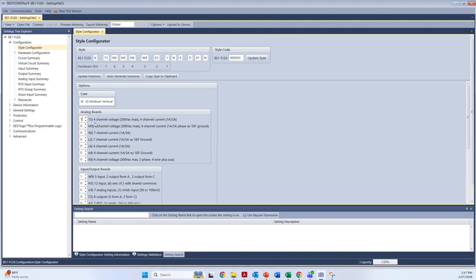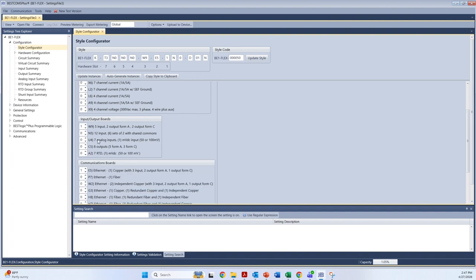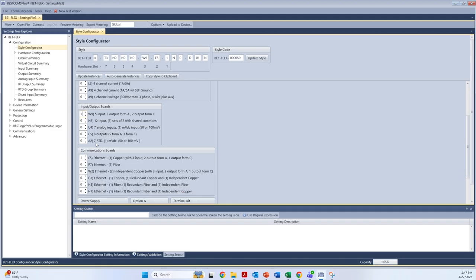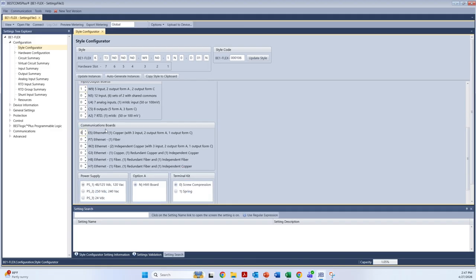So for this application, for 3 voltage phase inputs, we will use the 4-channel voltage and 4-channel current for the 3 current inputs for phase A, B, and C, which is a T3 card. Typical input-output board, I will use the W9, which has 5 inputs and 4 outputs, 2 of them form C. For communication boards, 1, 2, or 3 Ethernet port options. For this option, we'll use W2, which is 2 copper inputs, RJ45, with 3 inputs and 3 outputs.